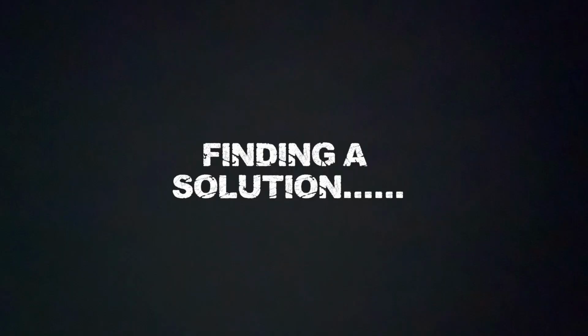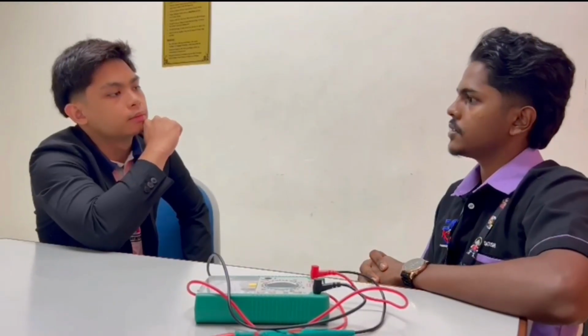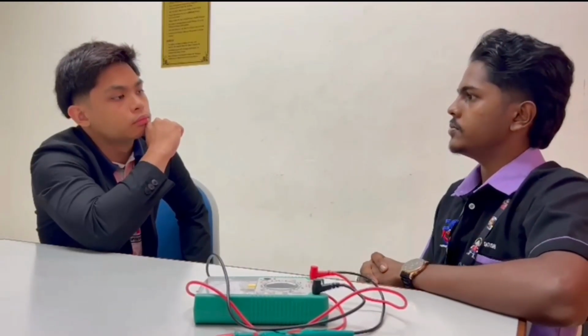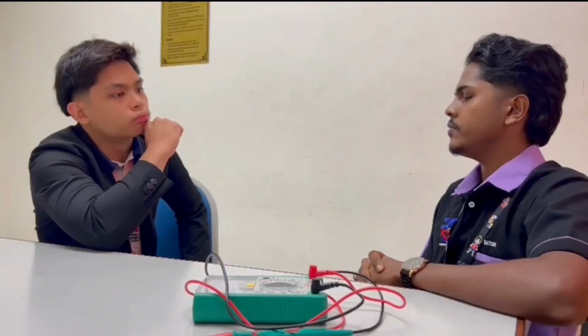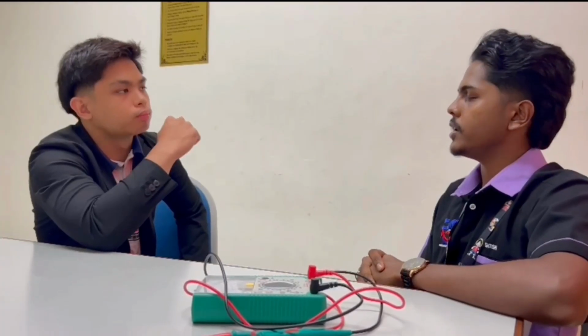What does that mean for the equipment? It means the monitor may continue giving incorrect readings. I will recommend sending it for service. So, what should we do now? We need to send the monitor for servicing and recalibration. After that, we will perform the test again with the reference device. And if it passes? Then we can return it to the ICU. But if it fails, we might need to investigate whether a component needs to be repaired or replaced.